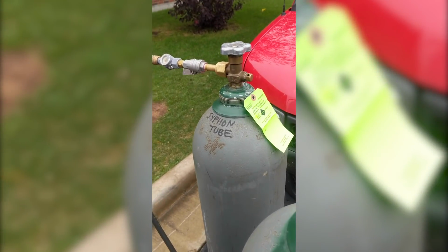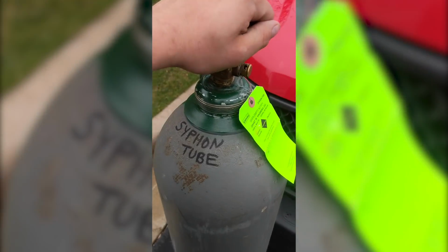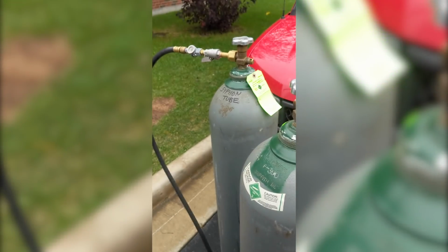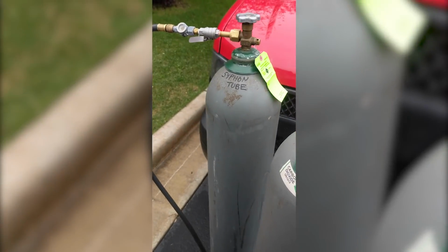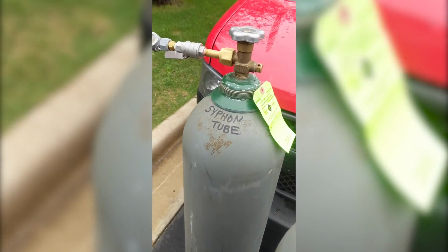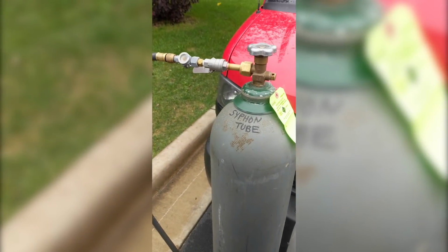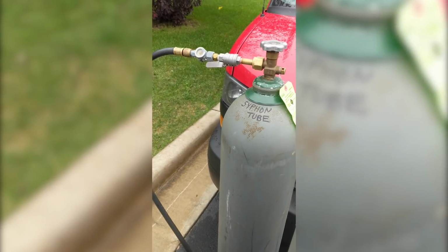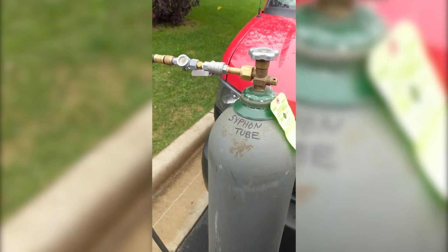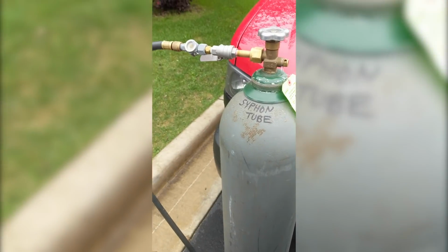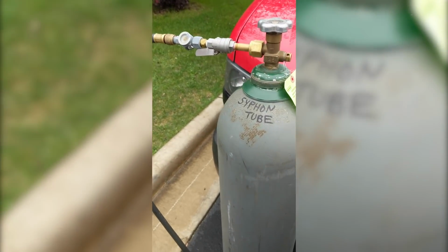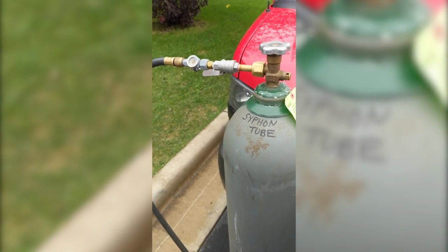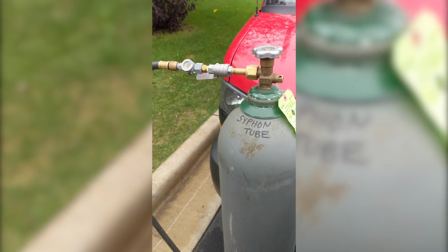So we're adding the CO2 in right now out of these siphon tube bottles that have a dip tube in them to allow liquid to come out like a refrigerant tank would. And we're just waiting for the sight glass to stop flashing. There's no really other way to do it besides having a pressure gauge on there. Not really worried about the hose blowing out of the sight glass. I mean, it's going into a vessel. It's 4 times as large as the tank, only running 500 pounds.